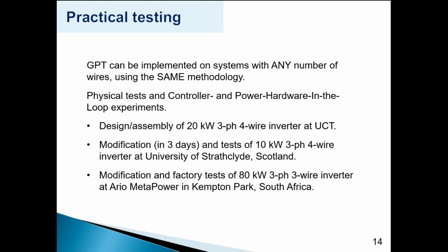We've also looked at it in terms of practical testing. We've carried out physical tests and controller and power hardware in the loop experiments. So the way we did this is we designed a completely new 20 kilowatt three-phase four-wire inverter at UCT. We assembled it. It's a three-level inverter, as I say, 4 wires. And that inverter is controlled using the general power theory. Then skipping to the bottom, we modified an 80 kilowatt three-phase 3-wire inverter, which is a commercial inverter made by Ario MetaPower, who are based in Kempton Park.